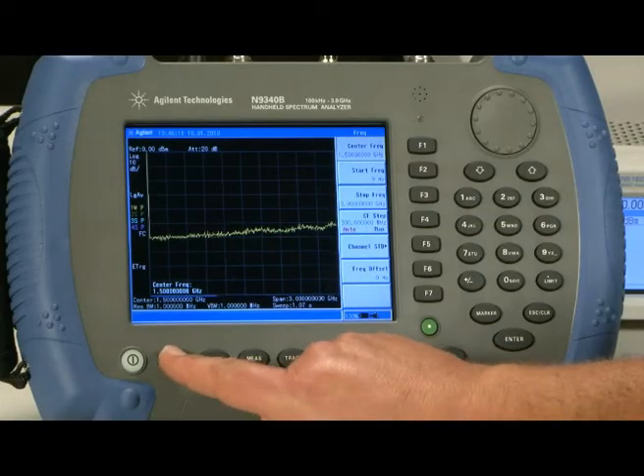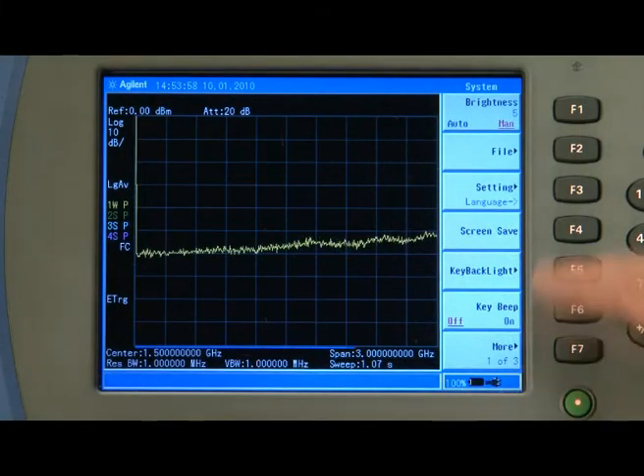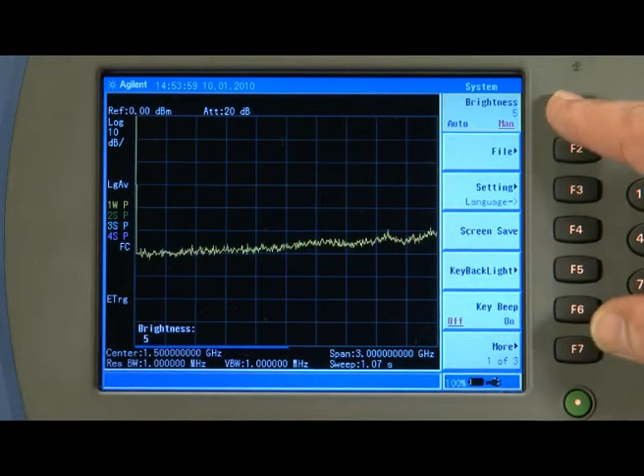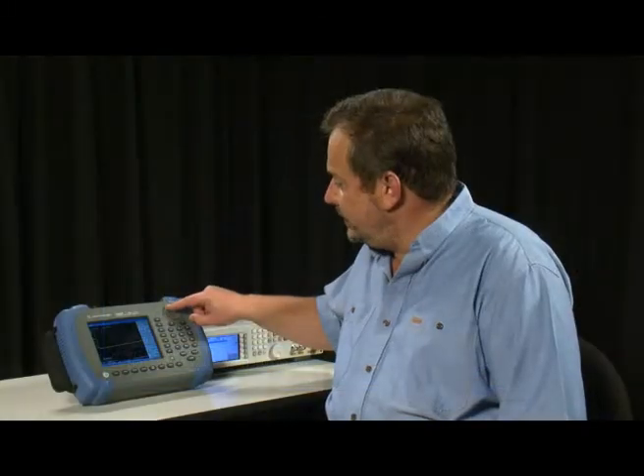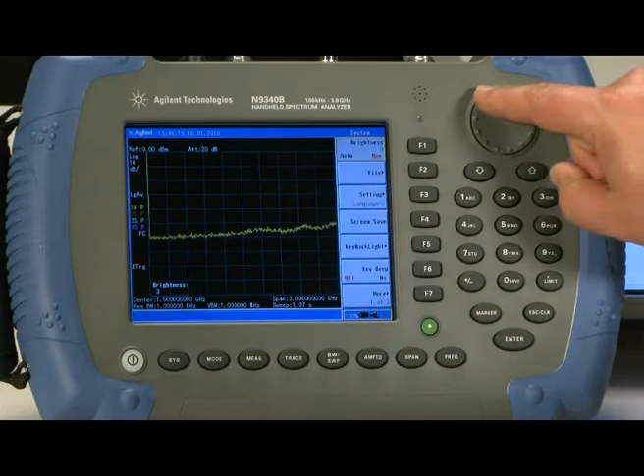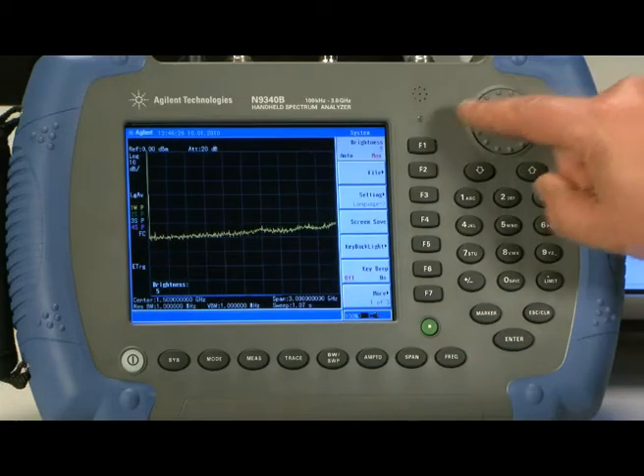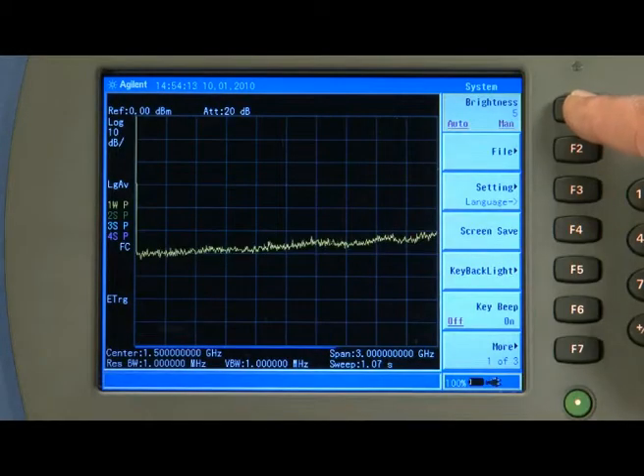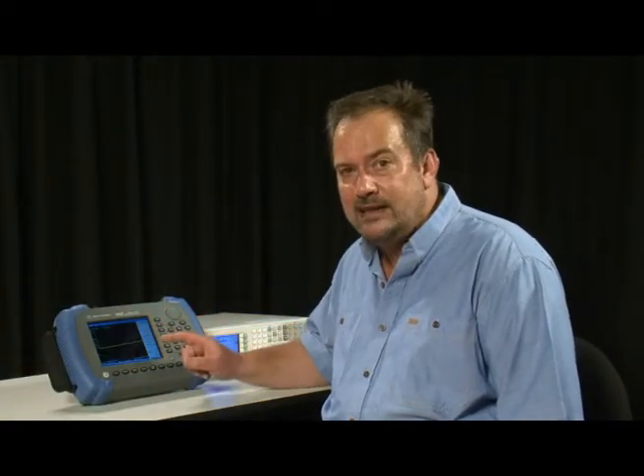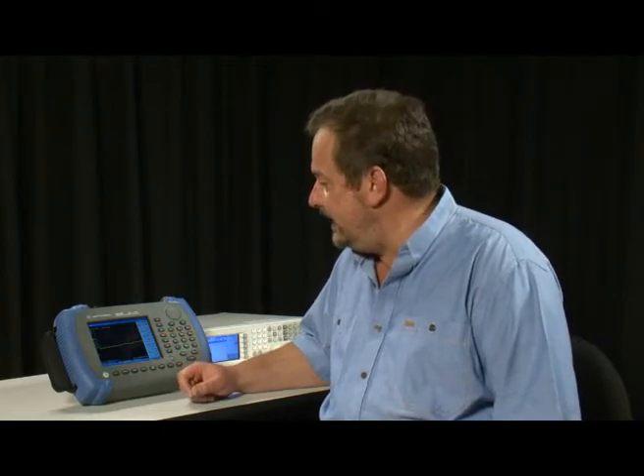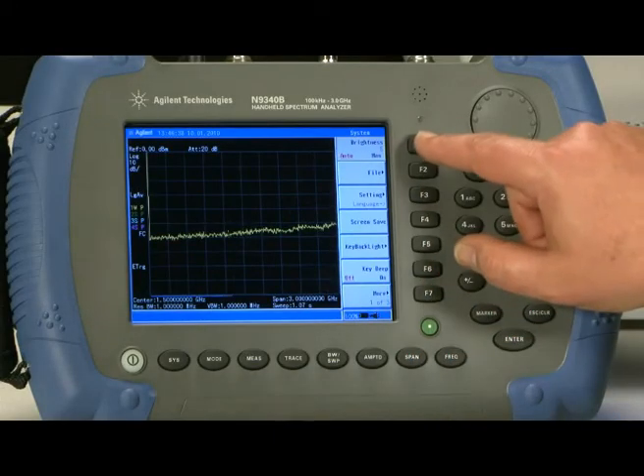If I press the system button you can see here there is a button called brightness. If I press that you can see it is set to manual and level of 5. I can turn the knob and make the screen brighter or dimmer. If I press the button again it changes the brightness setting to auto. Now the light sensor is active and the screen brightness will be automatically adjusted depending on the ambient lighting conditions. I will set that back to manual for now.